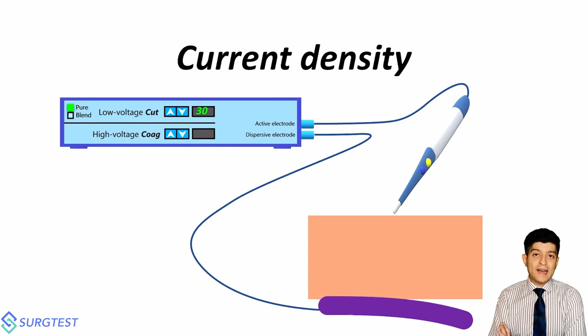Now, say for whatever reason, I have not attached my dispersive electrode that well and it's coming off on one side. Well, you can see the energy delivery staying the same. The current density on the dispersive electrode side is actually increasing, right? This is seeming a little unsafe. So let's make it even more unsafe right now and make it an even narrower attachment to the patient body. And you can see at this point, the current density has gotten extremely high on the dispersive electrode side.